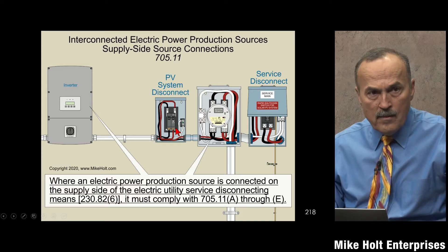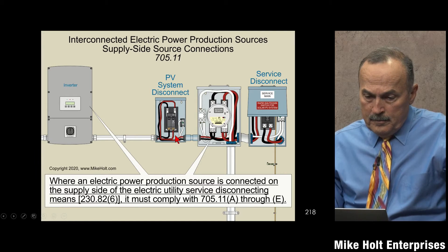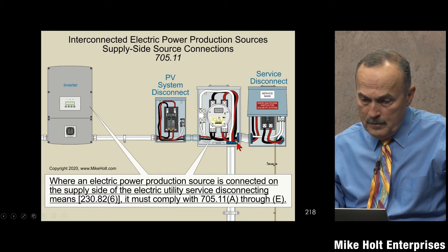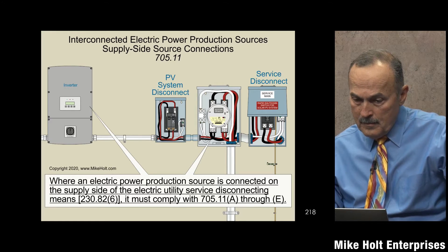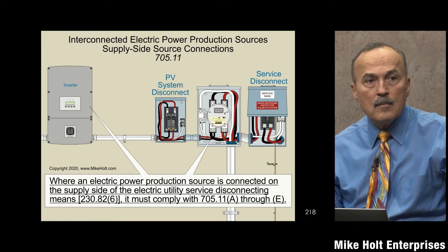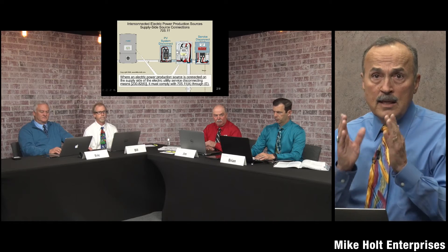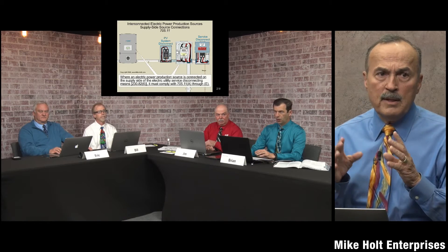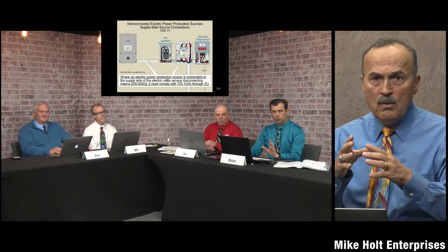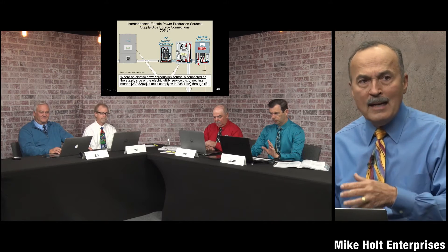A note on that diagram: there's a meter base there. From the National Electrical Code point of view, that's legal, but some utilities may question using double barrel lugs within a meter base while others will allow it. It's something to be aware of — it's legal per the code, but whether it's permitted by the utility varies. If the utility says no, you'll need to go to the disconnect, add a wireway, or use a box to make that supply side connection.